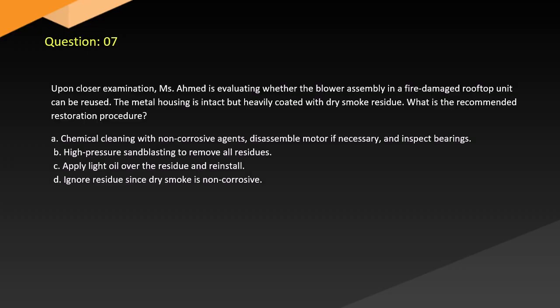Question 7. Upon closer examination, Ahmed is evaluating whether the blower assembly in a fire-damaged rooftop unit can be reused. The metal housing is intact but heavily coated with dry smoke residue. What is the recommended restoration procedure? A. Chemical cleaning with non-corrosive agents. Disassemble motor if necessary and inspect bearings. B. High-pressure sandblasting to remove all residues. C. Apply light oil over the residue and reinstall. D. Ignore residue since dry smoke is non-corrosive.